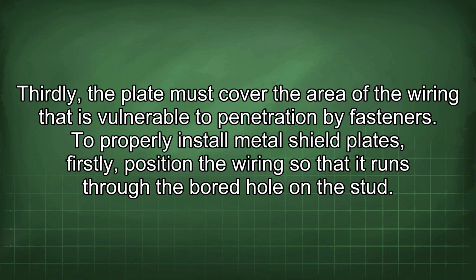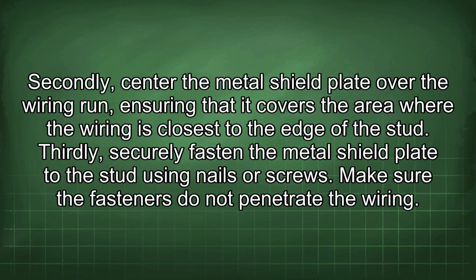To properly install metal shield plates, firstly, position the wiring so that it runs through the bored hole on the stud. Secondly, center the metal shield plate over the wiring run, ensuring that it covers the area where the wiring is closest to the edge of the stud. Thirdly, securely fasten the metal shield plate to the stud using nails or screws. Make sure the fasteners do not penetrate the wiring.